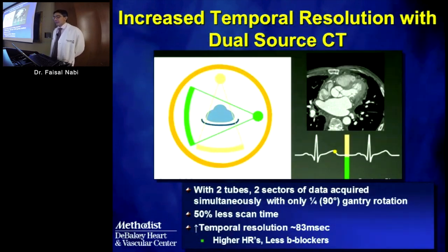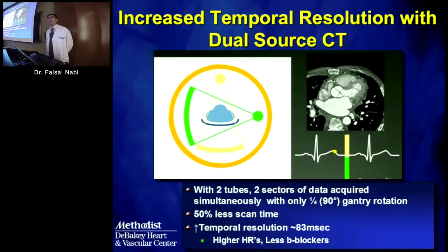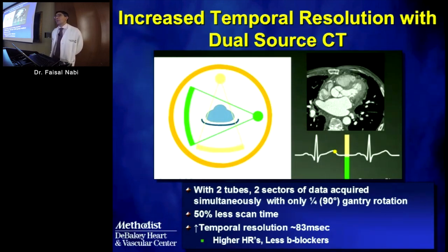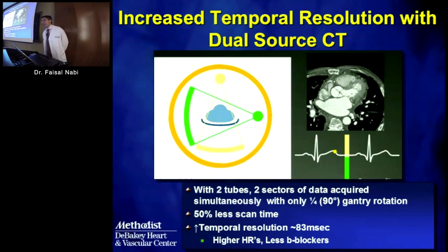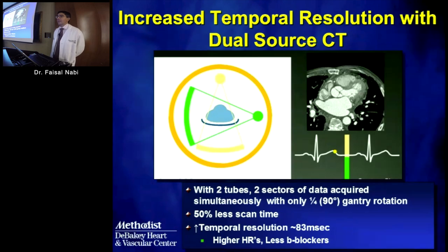Dual source CT is the solution in 2015 and beyond. With two detector heads at 90 degrees to each other, only a quarter gantry rotation is required to create an image. Therefore, temporal resolution is one-fourth of the gantry rotation time—330 milliseconds divided by four equals approximately 83 milliseconds. This allows imaging at higher heart rates while still obtaining still images, and increases lab throughput without being as aggressive with beta blocking.